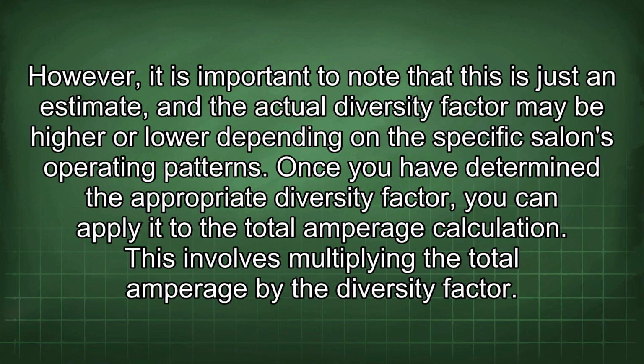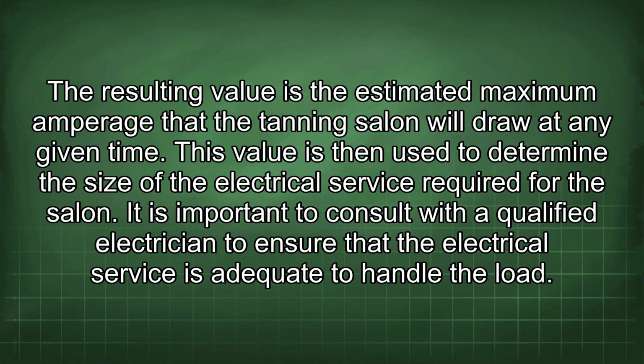However, it is important to note that this is just an estimate, and the actual diversity factor may be higher or lower depending on the specific salon's operating patterns. Once you have determined the appropriate diversity factor, you can apply it to the total amperage calculation. This involves multiplying the total amperage by the diversity factor. The resulting value is the estimated maximum amperage that the tanning salon will draw at any given time. This value is then used to determine the size of the electrical service required for the salon.